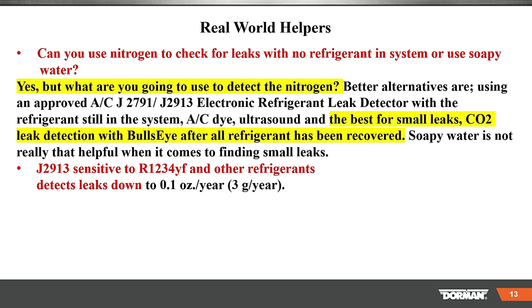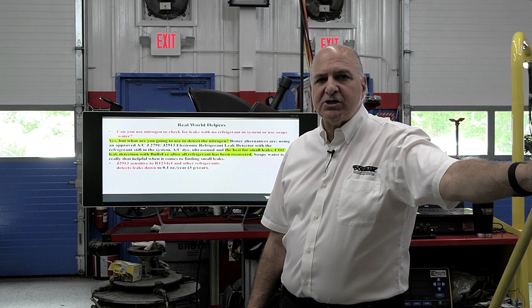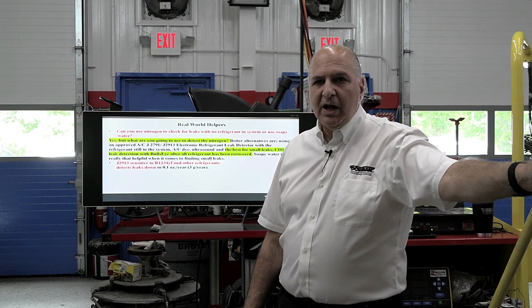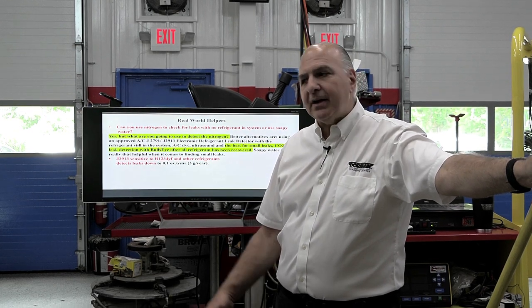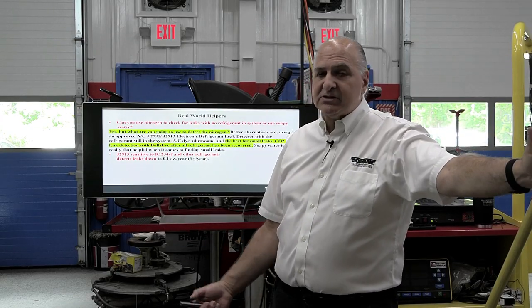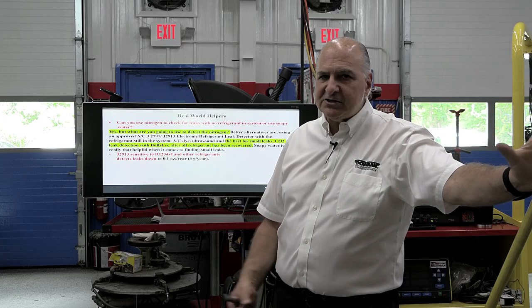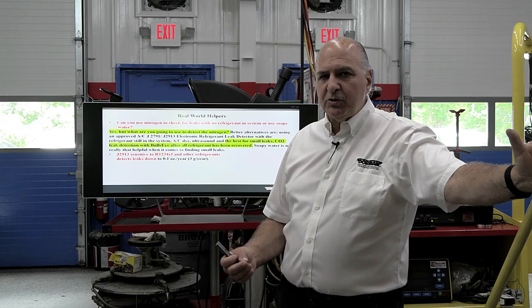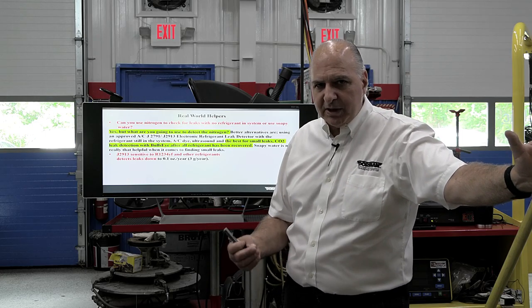But what we do is we test the system with CO2 first, and we have found leaks that that special leak detector doesn't find. And it doesn't mean the brand is bad or whatever. CO2 is a smaller molecule than the R1234yf.